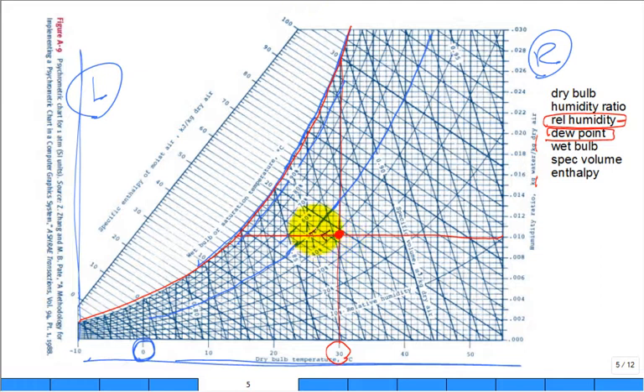Do this thought experiment. If I move in this direction along this line, how could I do that? Well, I'm not changing the amount of water vapor in my moist air mixture. I'm just lowering the dry bulb temperature, right? How could that be accomplished? You just cool it. That's all you're doing. You're cooling it. What happens to the relative humidity? I cool it. Oh look it. Now it's 50%. Oh, I cool it some more. Look at it. It's 60%. It's 70%. It's 80. It's 90. You could cool it, not increasing or decreasing the amount of water vapor until you get to saturated air. What temperature do I have to cool it to in order to get it to be saturated air? 14 degrees C. They come over here. They brought it down and they looked and they said, oh, that's 14 degrees C.